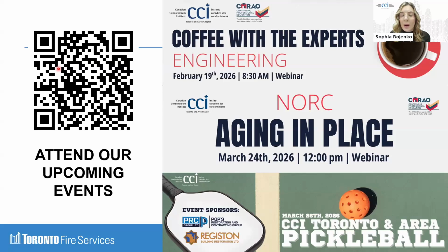Okay, if an EV car has a fire, is there a requirement to upgrade the volume of water if a fire occurs in the garage or replace water with another fire suppression system? No, there's no requirement. So even the new building code only refers to the 2019 NFPA 13, and that's still on the old system of water. Unfortunately, the sprinkler standard is just in the 2022 edition upgraded to get 33% more water for parking garages, but that's not in effect yet. Definitely not in effect. Nothing you could do for existing buildings.